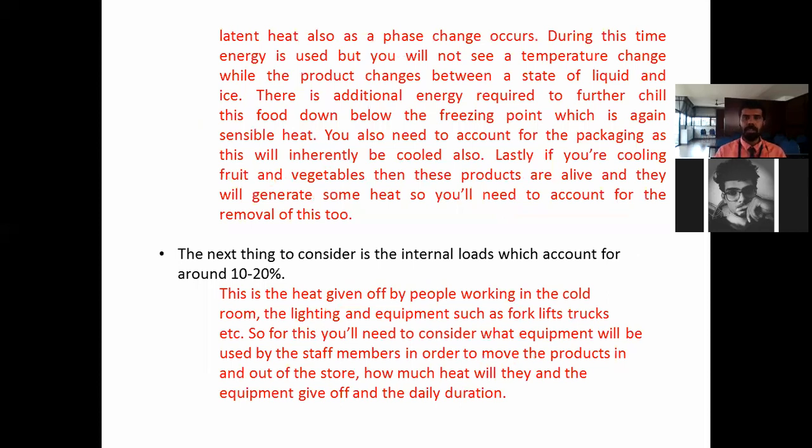During this time, energy is used, but you will not see a temperature change while the product changes between the state of liquid and ice, because of the latent heat. There is additional energy required to further chill this food down below the freezing point, which is again sensible heat.